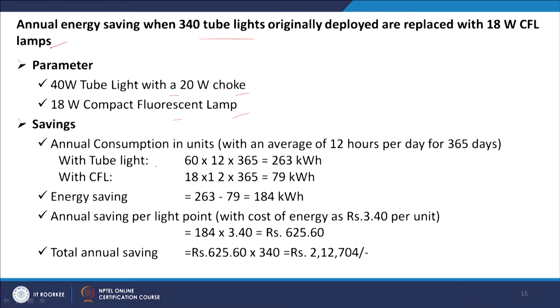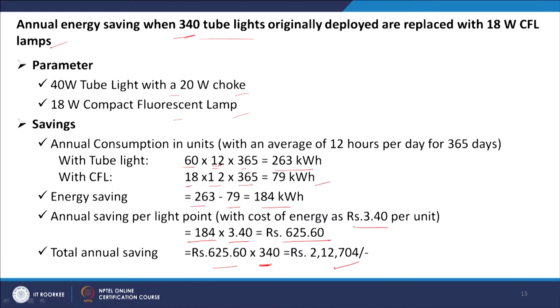With the tube light it is 60, 40 plus 20, into 12 into 365, that is 263 kilowatt hour, and for the CFL it is 18 into 12 into 365, where 12 is the average hours used per day. That is equal to 79 kilowatt hour. So, the saving is 263 minus 79, 184 kilowatt hour. The cost is, say, 3.40 rupees per unit. So, multiply this by this, and we get rupees 625.60 per tube. The total is 625 into 340, that is equal to this one. This is our annual saving. We have 340 tubes, that is why this is multiplied by 340. So, we are getting this much annual saving by implementing this project.